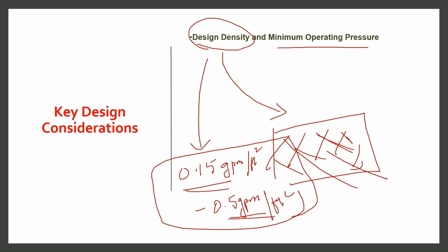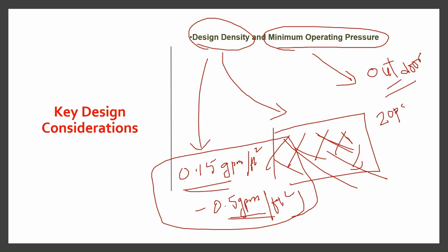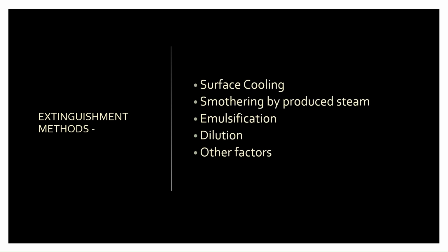And coming back to the minimum operating pressure of any nozzle protecting outdoor hazards, please make a note of it, outdoor hazards shall be 20 psi as per NFPA 15. Now let us talk about extinguishment methods before we move further. This is the very heart of any water spray system. We need to understand how water spray system controls burning and what makes it effective.